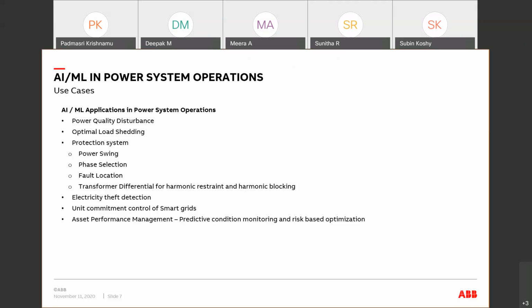But there are some ML models based on supervised learning that have successfully implemented fault classifiers, which can be effectively used both for conventional and non-conventional energy sources. Invariably, when you're using the current component, which is the most used component for doing the phase selection, there is always a shortcoming whenever a distributed energy resource, a non-conventional energy resource, is introduced into the system. So this can change when you are looking at a machine learning based solution for phase selection. Fault location is very similar.